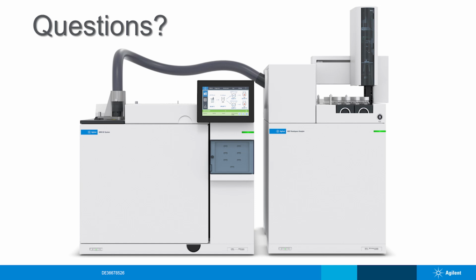The one thing to monitor for is if you are doing a lot of shaking. If you have to really agitate your sample on high levels of shaking, you might check for contamination, just to make sure that the shaking isn't contaminating your probe. So run blanks and make sure that your system's clean after you run a sample. But no, I think volatiles in water uses a 10 ml sample. There are several well-published applications out there that do use larger volumes. So totally okay in a 20 milliliter vial.